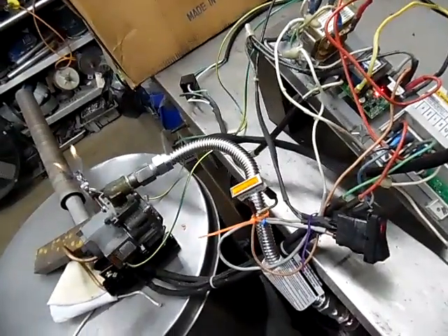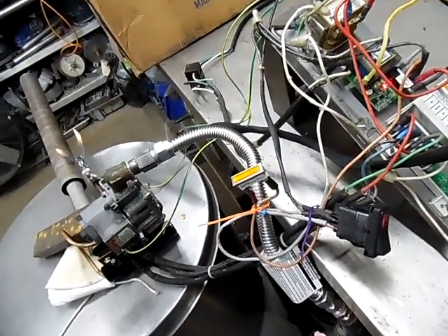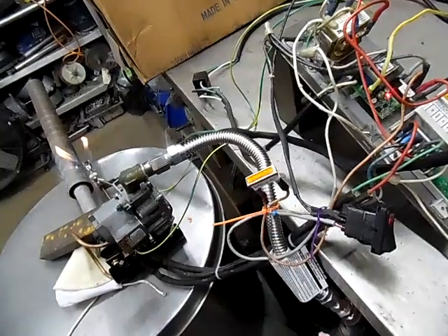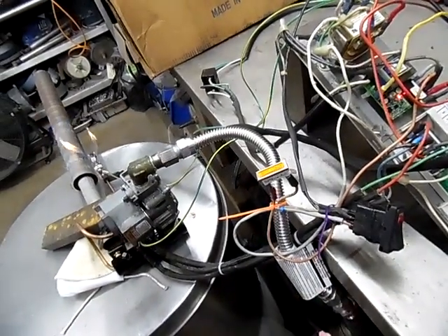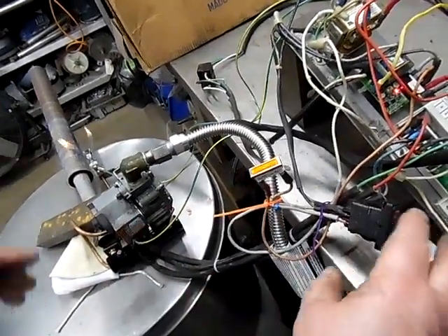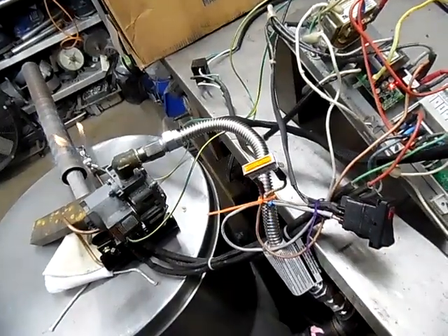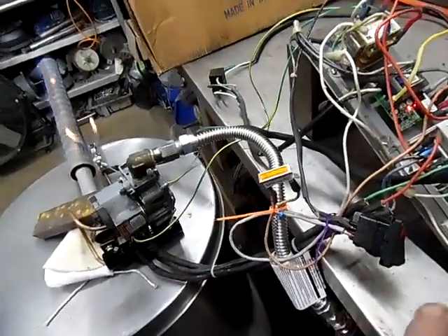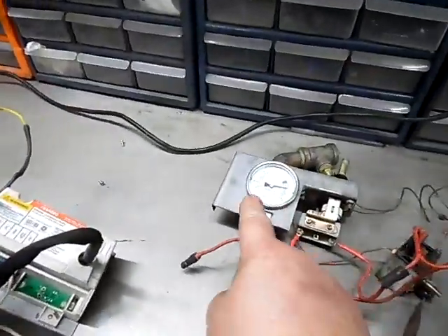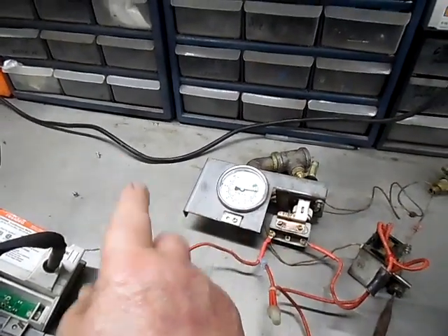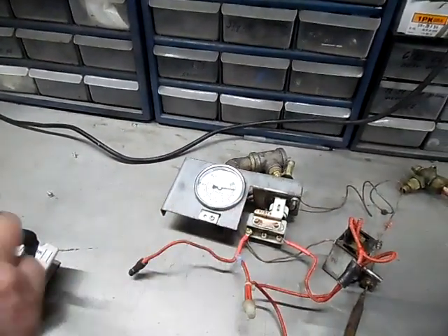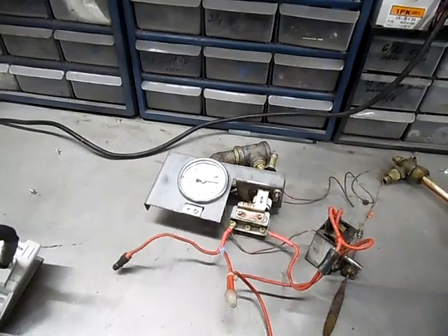It came on. The valve came on. See, I didn't have any thermostat or pressure switch hooked up. It went right to it. So this is a great way to bypass these two components over here. Bypass the pressure gauge in this, and then you can go back and see what's going on there. So it's a great way to make sure if your system's working.